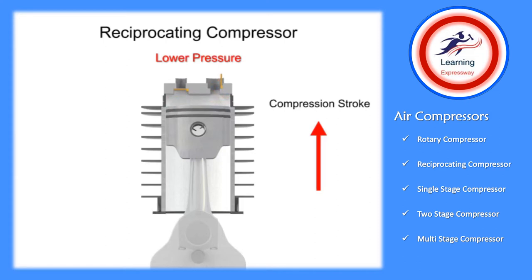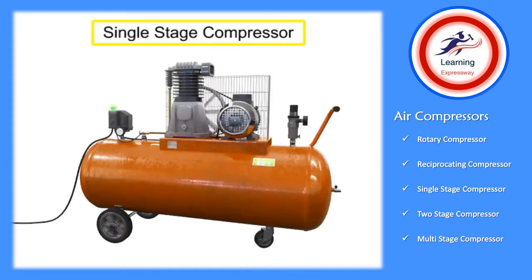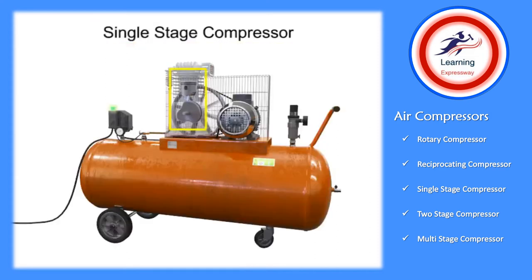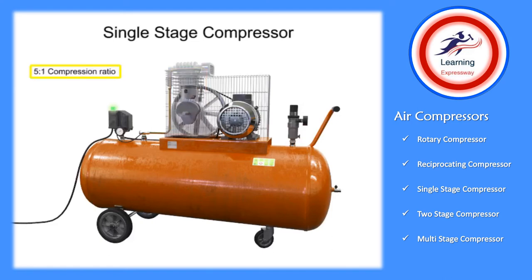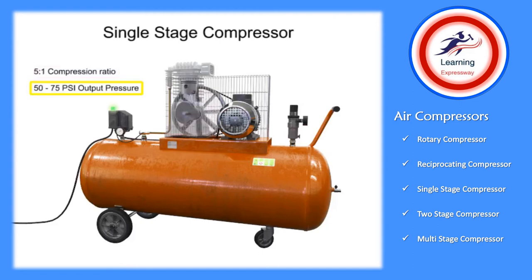This is a single-stage compressor. It has only one piston and cylinder and compresses the air in only one stage. A single-stage compressor typically has a compression ratio of 5 to 1 with an output pressure of about 50 to 75 psi.